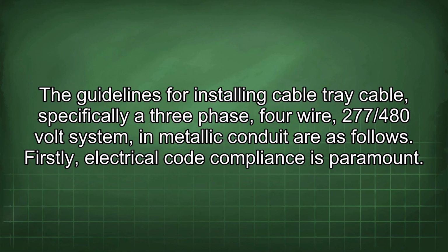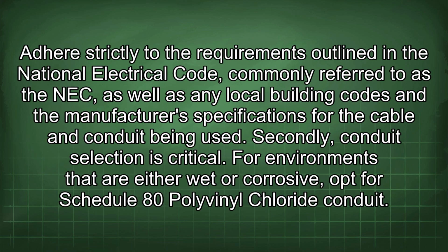The guidelines for installing cable tray cable, specifically a 3-phase 4-wire 277/480 volt system in metallic conduit, are as follows. Firstly, electrical code compliance is paramount. Adhere strictly to the requirements outlined in the National Electrical Code, commonly referred to as the NEC, as well as any local building codes and the manufacturer's specifications for the cable and conduit being used.